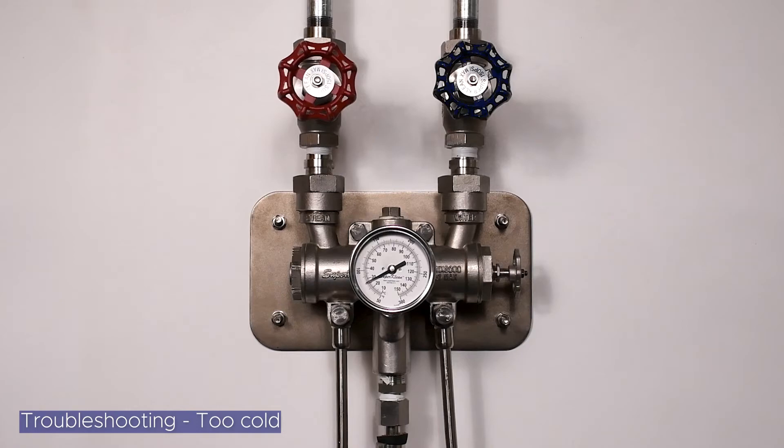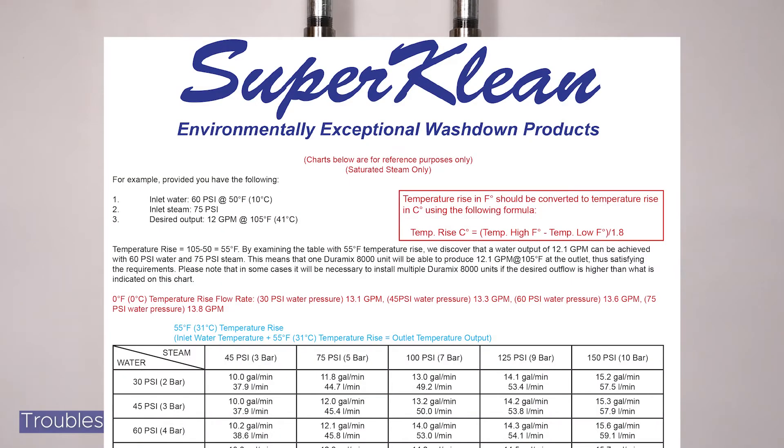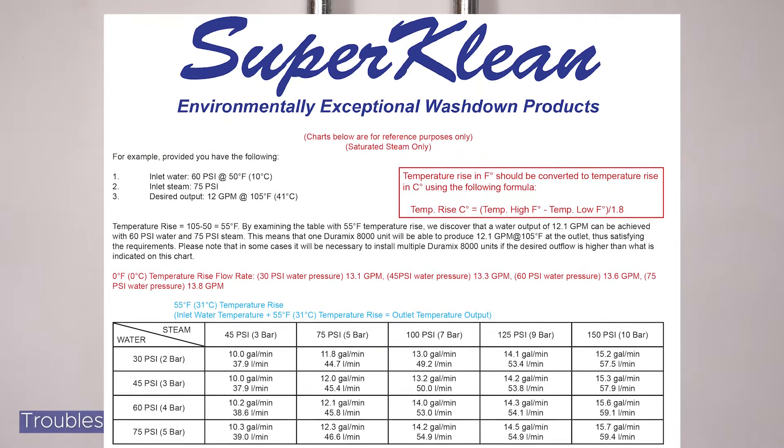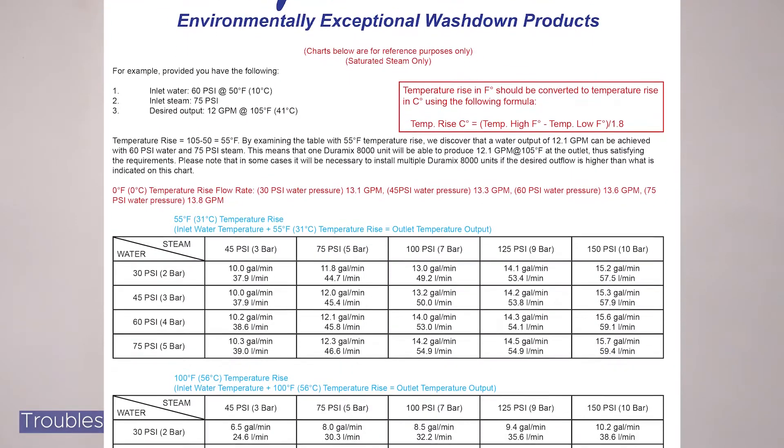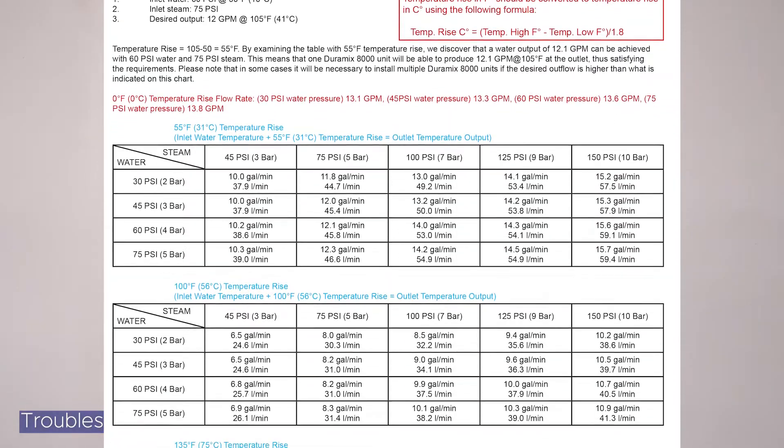Adjusting the cold water globe valve can affect the water output. Low water output could be due to low steam pressure in your factory relative to the cold water pressure. To get a rough idea of your flow rate at a certain temperature, please refer to the temperature rise versus flow rate output chart.